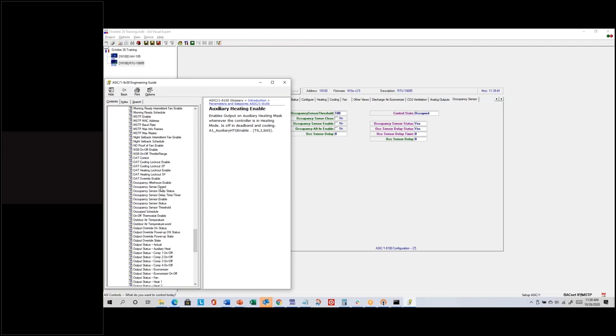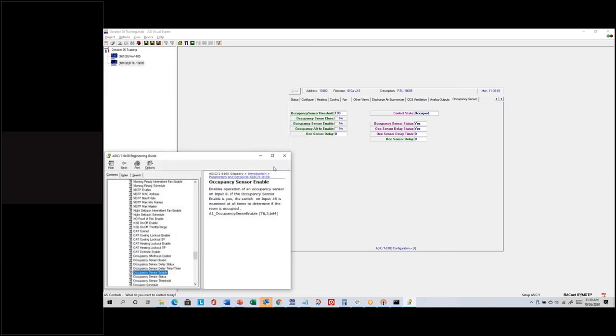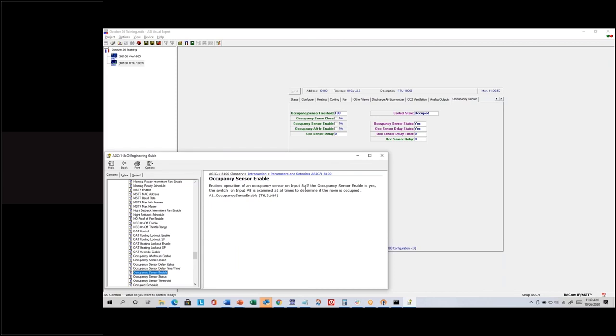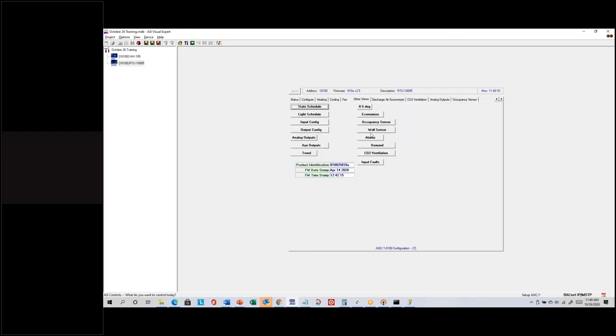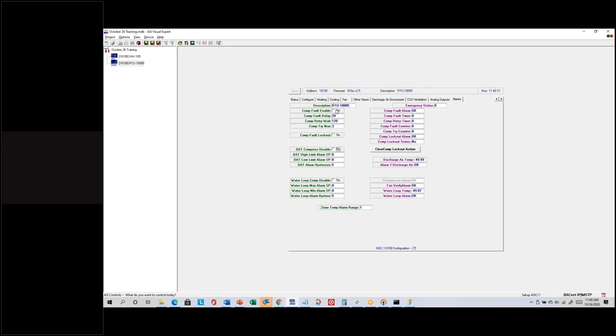The glossary says: occupancy sensor enable allows operation of an occupancy sensor on input 8. It can work with either close contacts being occupied or close contacts being unoccupied — that's what 'occupancy sense closed' means. If occupancy sense closed is yes, that means closed contacts equals occupied. That's available in both ASC 1s. There are also compressor alarms you can monitor via an input to see if there's a compressor fault. If discharge air temperature gets too high or low, you can get a discharge air alarm and optionally disable the compressor. Water loop alarms are available too — if water loop temperature gets out of range you can disable compressors.